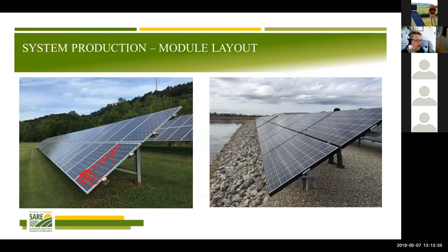And actually all of them would probably be too if the snow piled up. While if the snow started to melt and piled up and only covered the bottom part of this one, this thing is still two thirds functioning, because the part that has sun on it would function, because these are in series together, actually broken here with three strings of cells. So there is some potential in a high snow area where you could gain at least a few percent of production by putting them in landscape mode. I'm not sure that's a real serious design consideration, but it is something that others have thought about when installing systems in snowier areas.